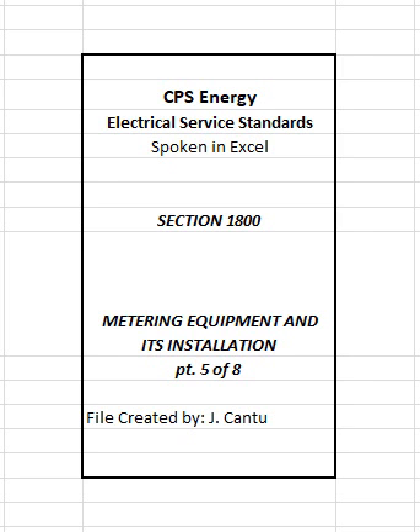1807.1 Front clearance. There must be a minimum of 3 feet of unobstructed space in front of self-contained meter sockets, and 4 feet of unobstructed space in front of transformer-rated meter sockets and instrument transformer enclosures, measured from the front surface of the socket or enclosure. The final grade or floor in front of the metering equipment must be level and provide a stable standing surface.